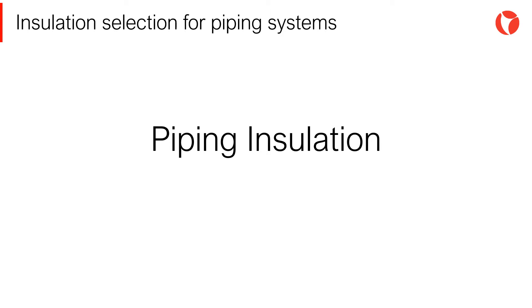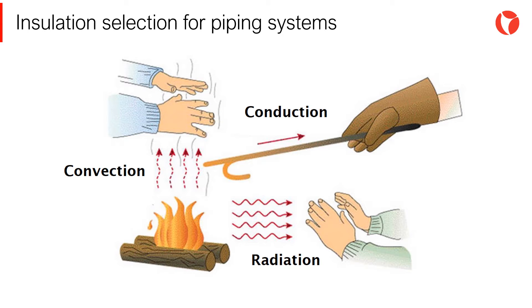Cold line insulation helps to reduce condensation on the outside of the piping system, which in turn helps to reduce corrosion. There are three types of heat transfer fundamentally: conduction, convection, and radiation. All three types act in a piping system simultaneously. However, it is usual to consider only heat conduction in the insulation element, since it normally governs the calculation.